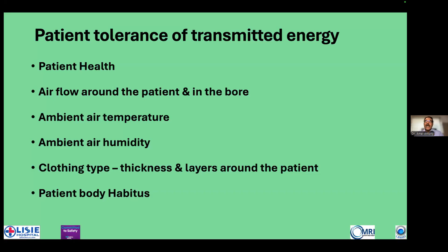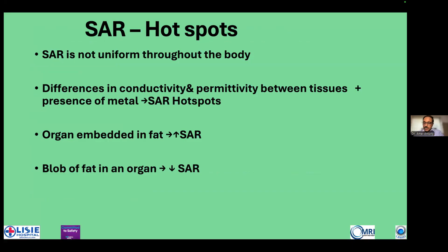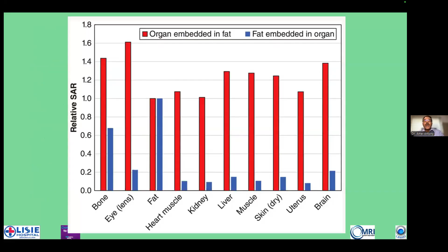And the patient tolerance also depends on the patient health and airflow within the bore, the ambient air temperature, how much the humidity is controlled, the clothing type of the patient, and also the body habitus. And remember, the deposition of this energy is not uniform throughout the body. An organ embedded in fat, like for example the kidney, which is completely surrounded by perinephric fat, the deposition of energy will be much higher as compared to an organ which has fat within, where the specific absorption rate would be much less. Now that's a graph which shows how organ embedded in fat and fat embedded in organ cause difference in SAR.